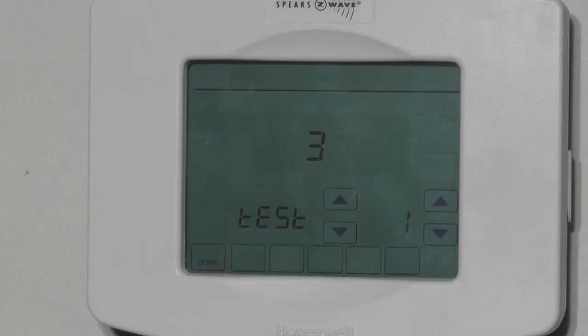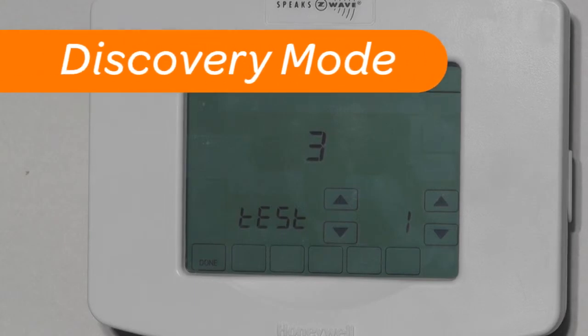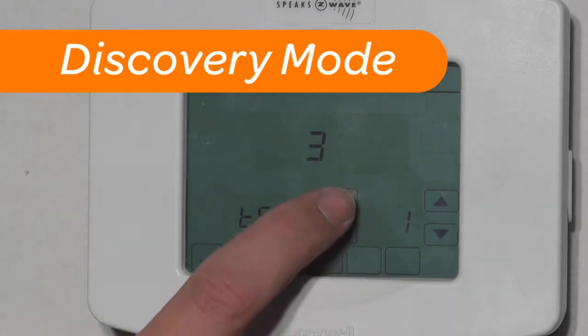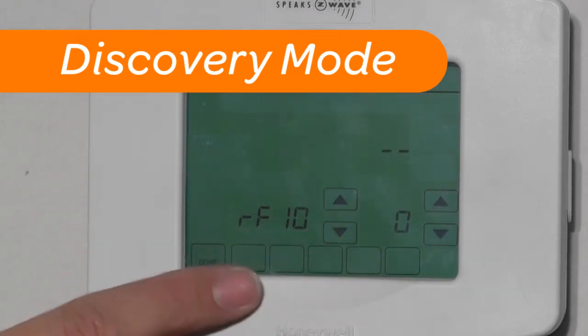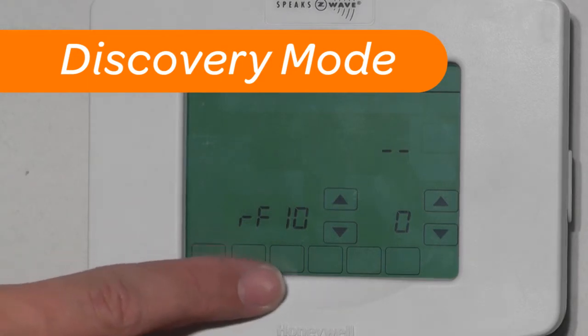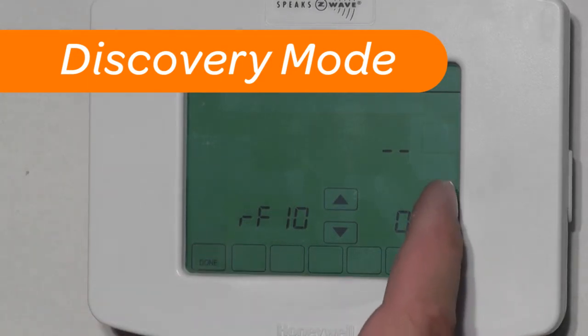After testing the thermostat and verifying proper operation, the next step would be to discover the thermostat into the DLC. Once the DLC is up and running and in discovery mode, use the up arrow on the left-hand side to scroll to RF10. On the right-hand side, press the up arrow to start the discovery process.